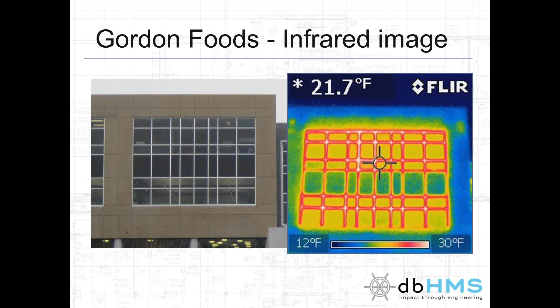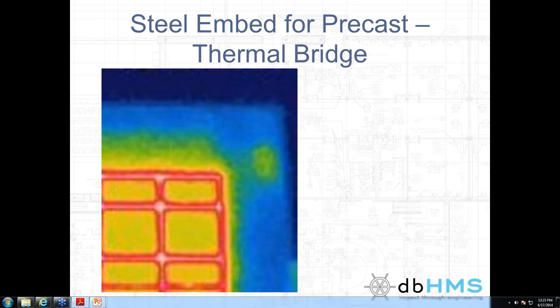This green dot in the upper right-hand corner represents the spot on the precast where the embed for the steel is that holds the precast onto the building. That embed has to penetrate through the spray foam insulation, and that's a good example of a thermal bridge. You can see it's represented here as maybe 15 degrees Fahrenheit warmer surface than the rest of the precast. Next slide.